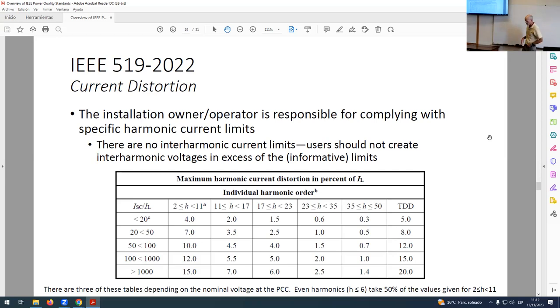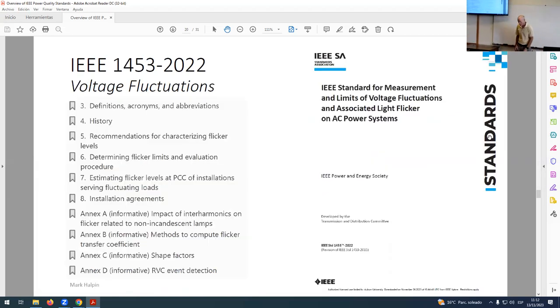As far as the current distortion limits, you may be aware that in IEEE 519, there are actually three of these tables, and these tables simply give limits for individual harmonics and total distortion amounts, right, depending on the size of the user with respect to the short circuit capacity and depending on the interconnection voltage. This is just one of the three tables. There's nothing new about these.